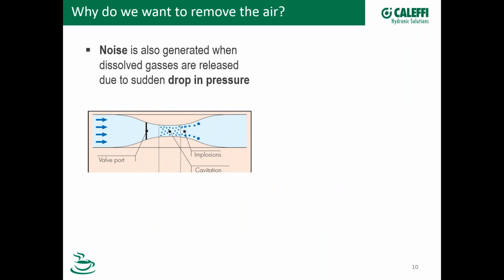Now this is a topic with a training session all by itself, but let's touch on it briefly here. So this example illustrates how cavitation can occur in a valve. When the fluid approaches a smaller cross-sectional area, as in a valve, the velocity will increase and the pressure will decrease. For example, if this incoming pipe were a 1-inch copper pipe with 6 GPM flow, that's about 2.2 feet per second velocity. And if this valve opening were a 1/2 inch, that velocity would increase to 7.6 feet per second. So there's a pretty big change.